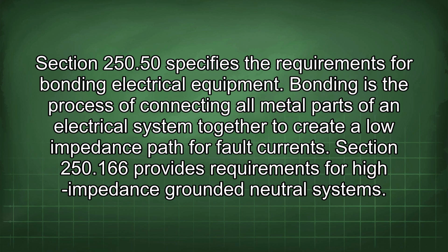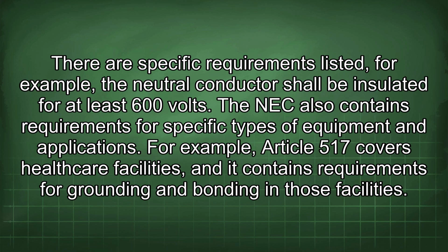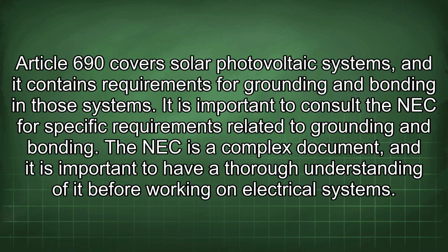Section 250.166 provides requirements for high-impedance grounded neutral systems. There are specific requirements listed. For example, the neutral conductor shall be insulated for at least 600 volts. The NEC also contains requirements for specific types of equipment and applications. For example, Article 517 covers healthcare facilities, and it contains requirements for grounding and bonding in those facilities. Article 690 covers solar photovoltaic systems, and it contains requirements for grounding and bonding in those systems.